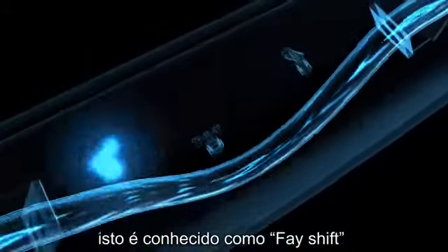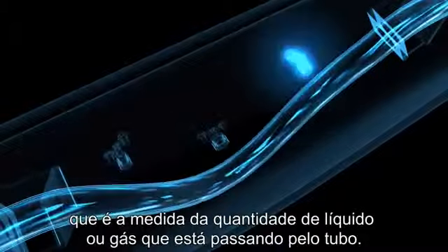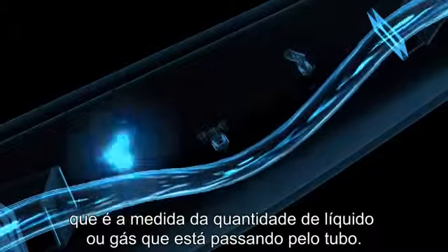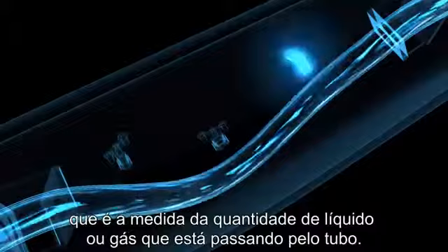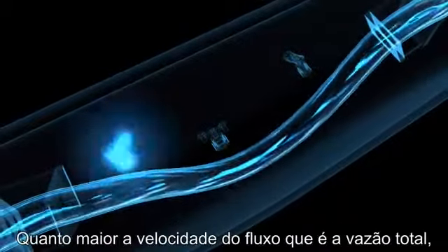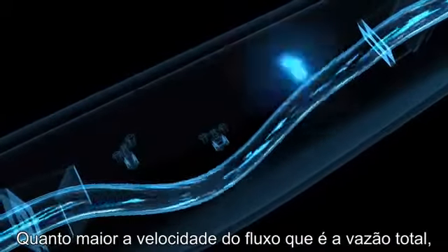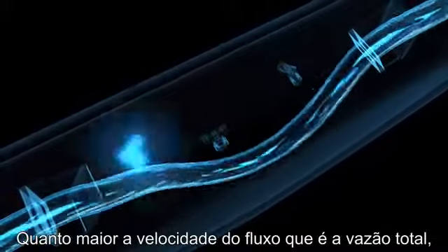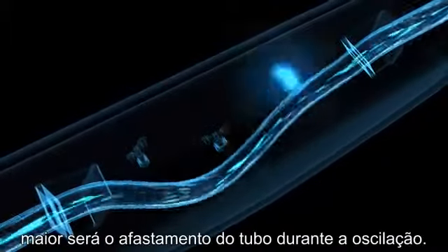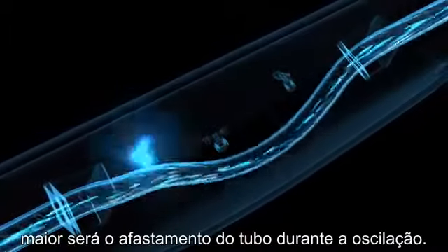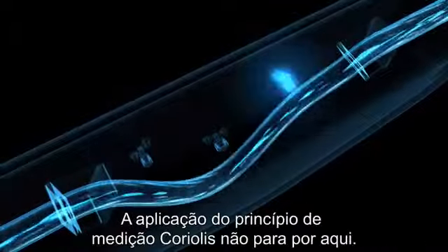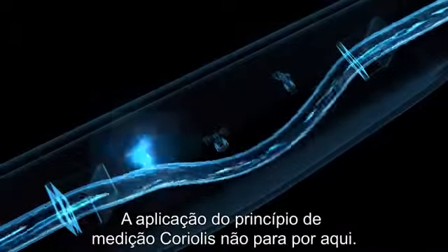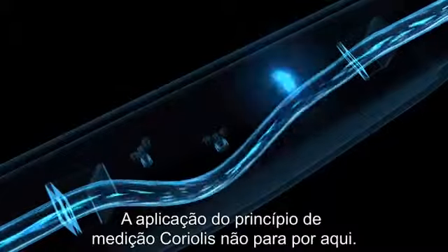This is known as the phase shift, and is a direct measure of how much liquid or gas is currently flowing through the pipe. The higher the flow velocity, and thus the total flow, the greater the deflection of the oscillating measuring tube. The application of the Coriolis measuring principle doesn't stop here.